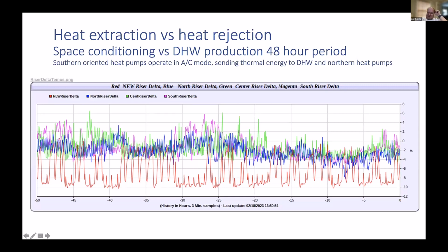The central portion of the building is the green line. Well, it doesn't have as much heat loss because it has much less outside wall. This is why it sometimes even has a positive 6-degree delta T, meaning it is actually operating in cooling mode sometimes, probably during the day in the middle of February. However, the northern side doesn't have that gain and is running in heating mode.